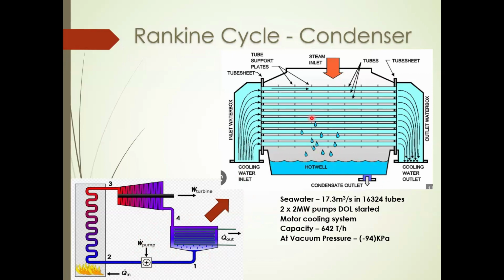Now this cooling water is taken from the Indian Ocean, of course. It is pumped by 2 megawatt pumps. Of course, because these are quite large, each has its own motor cooling system, lubrication oil system, gland sealing, all the things working in perfect condition in order to run these pumps. So its own auxiliaries have to be there if you want to run the pumps. Right.